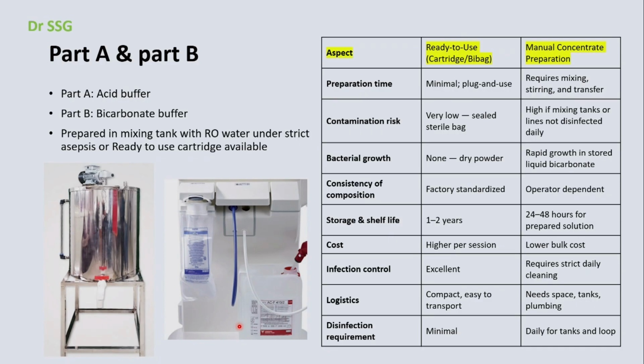So can we use that bag for 2 dialysis sessions? Not ideal, not advisable. It's available in 2 strengths, 600 and 900. So depending on the length of the session, you may use a smaller bag per session. The 900 provides you 150 liters, and your normal one dialysis uses 30 liters. So there is a lot of waste.